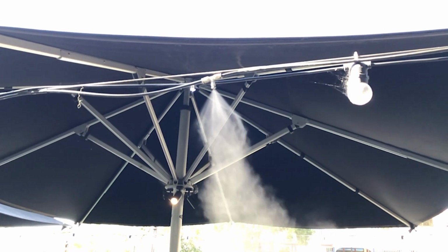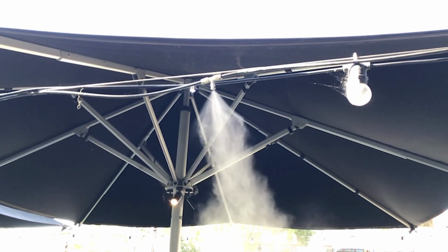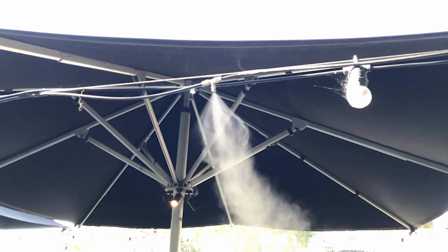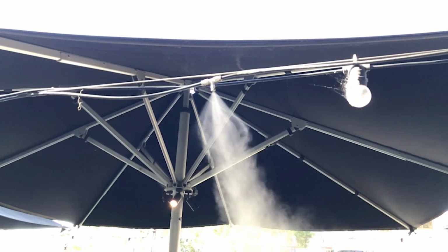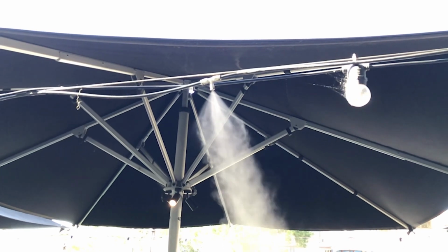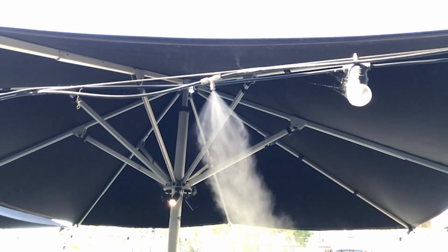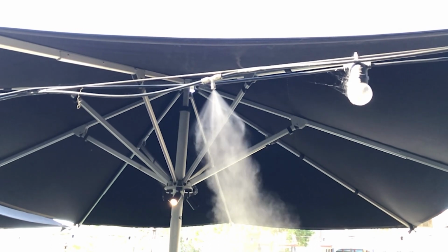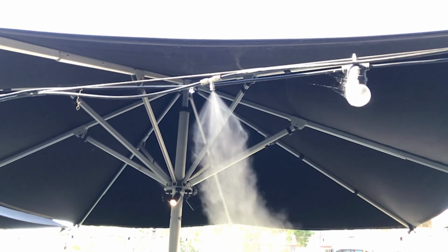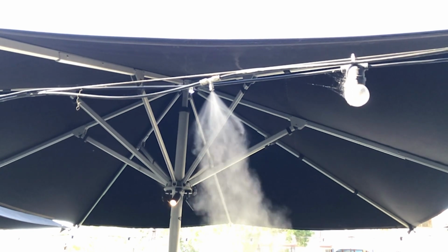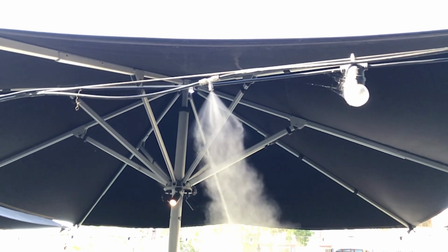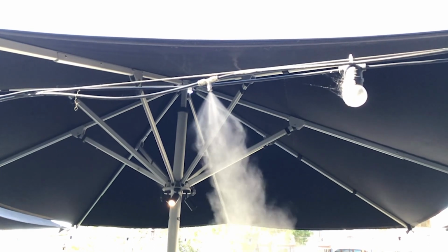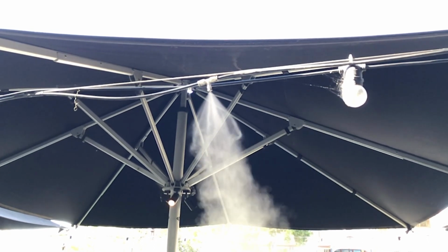One is that the tiny droplets evaporate while suspended in the air, which cools the air. The second advantage is that splitting water into millions of droplets dramatically increases the surface area and therefore evaporation rate. For example, if a 1 litre sphere of water is split into 15 trillion 5 micrometer droplets, the area of the water-air interface is increased by a factor of 25,000.